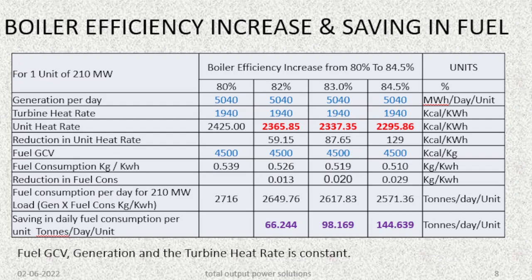When boiler efficiency increases, there will be a decrease in fuel consumption. The table depicts the boiler efficiency increasing from 80% to 84.5% in stages. The generation per day is 5040 MWh per day per unit. The turbine heat rate is 1940, taken as constant for all efficiency levels. The unit heat rate has decreased from 2425 to 2295.86 kcal/kWh when boiler efficiency increases to 84.5%, a reduction of around 129 kcal/kWh.